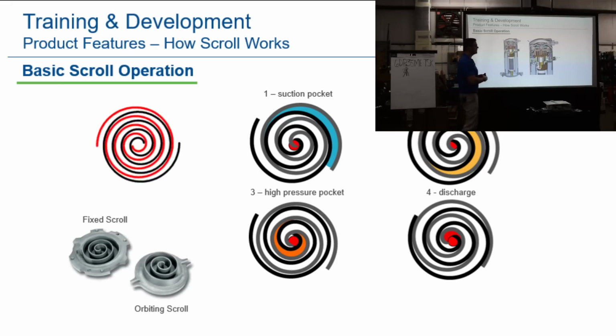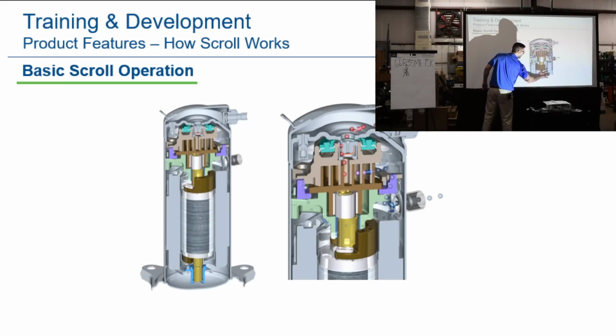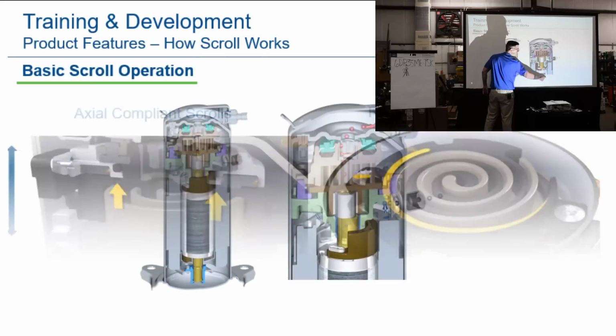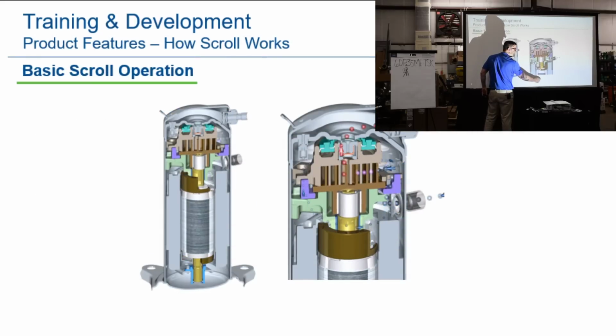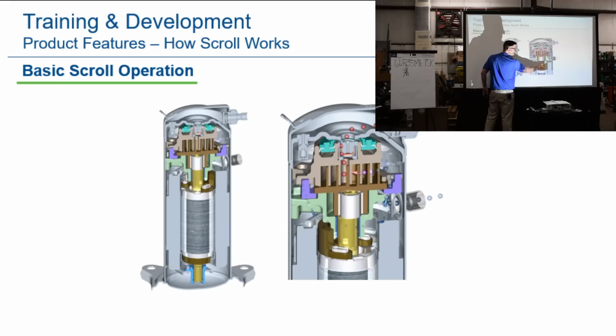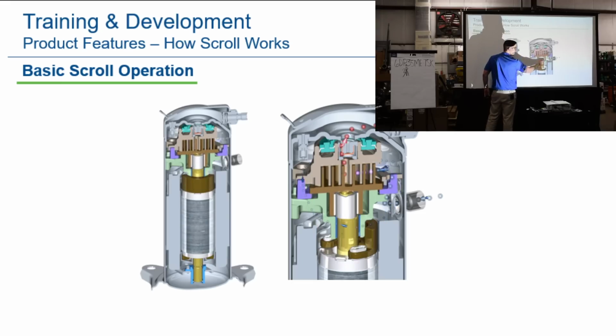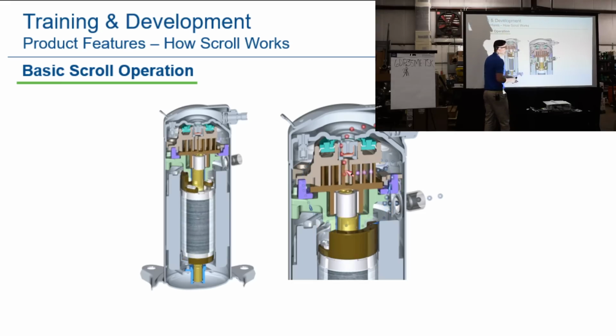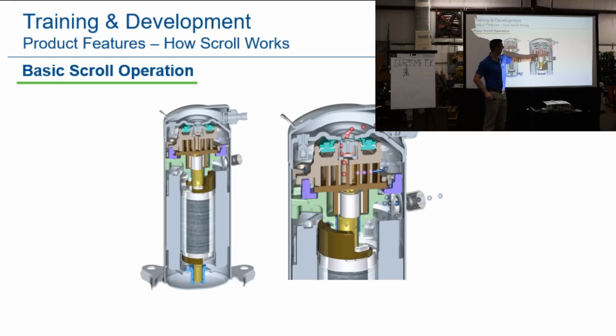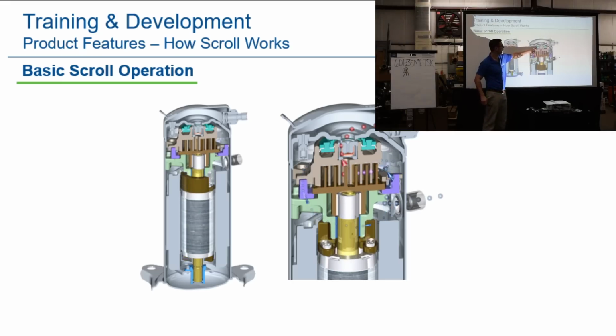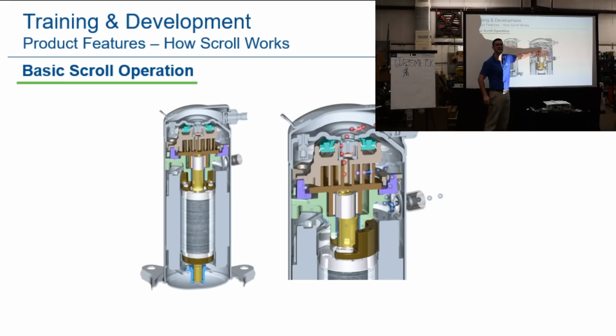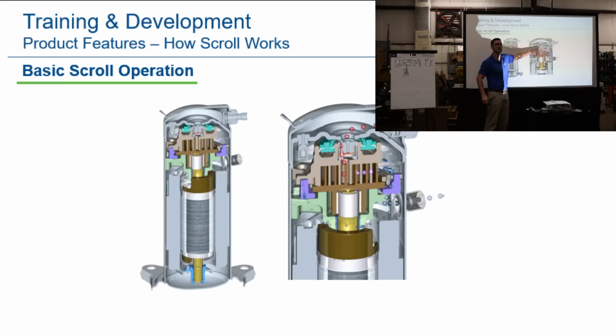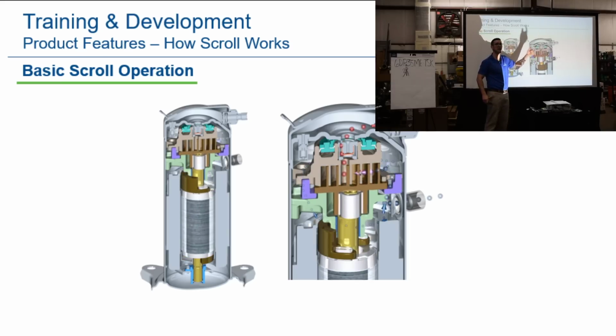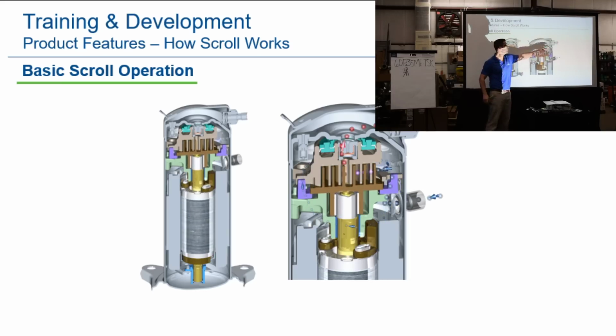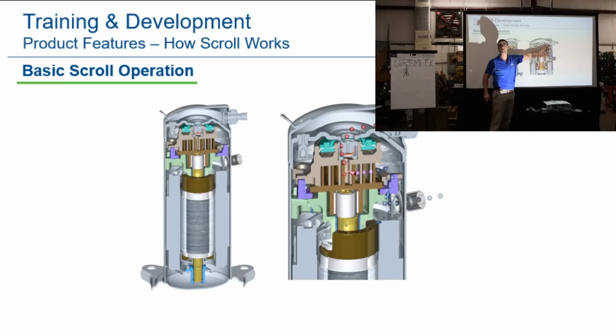This is how it works. You've got your suction gas coming in, cooling the motor. This is your stator. Here's your rotor. Here's your crankshaft. You've got a main bearing right here, and then a drive bearing. You've got an orbiting scroll right here and a fixed scroll, floating seal. This is an anti-rotation device right here, so it doesn't spin backwards. Then we've got another different check valve, a discharge check valve, right here.